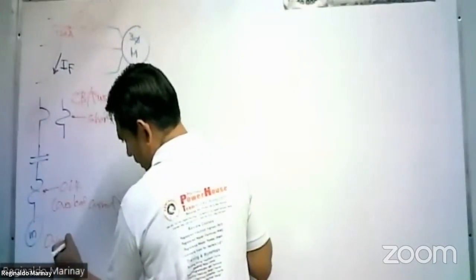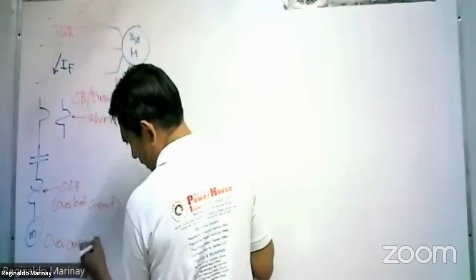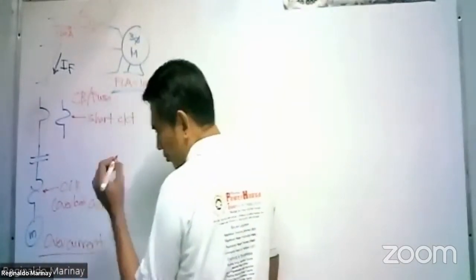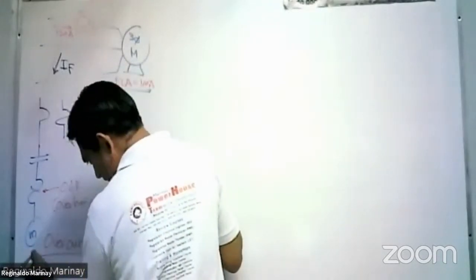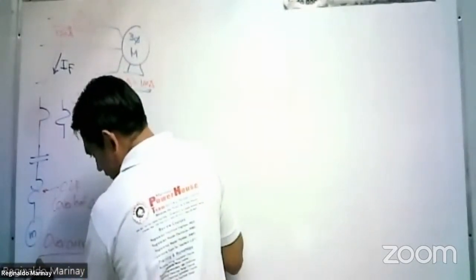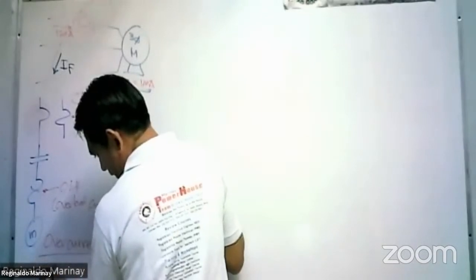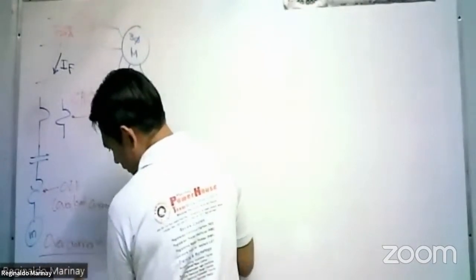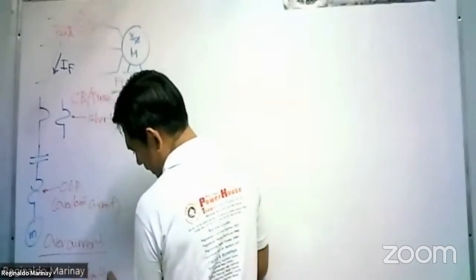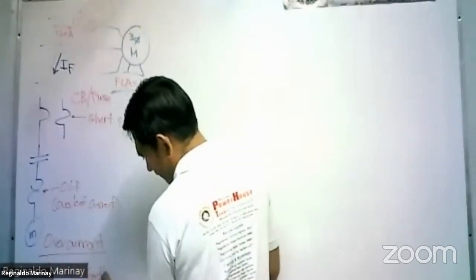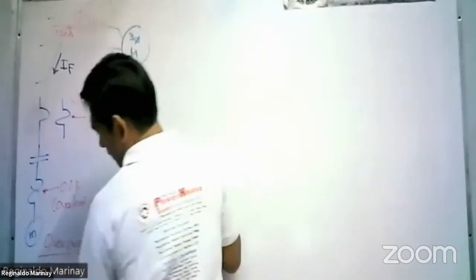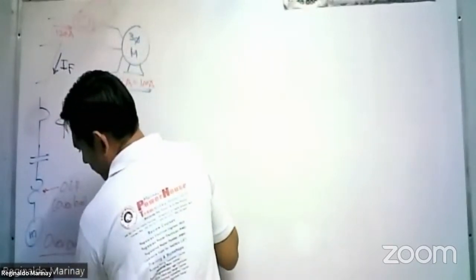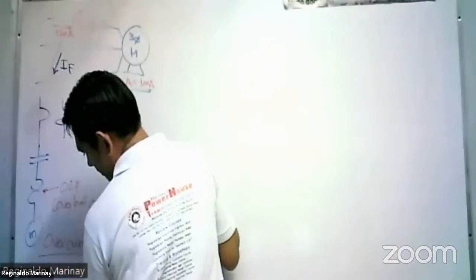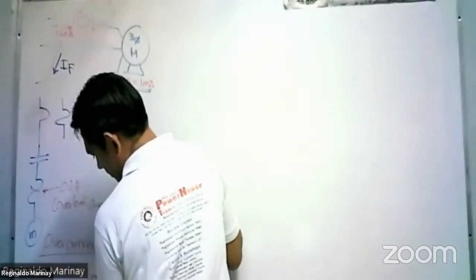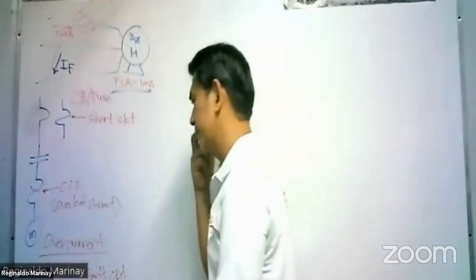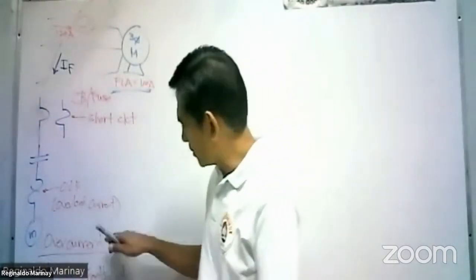What do we mean by overcurrent in the motor? Basically, if we mean overcurrent, we mean that is a short circuit current, or what we call the fault current. And then we have the overload current. Okay. Basically, there are two types of overcurrent.